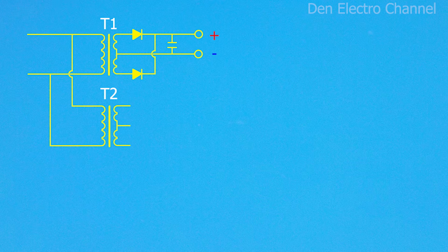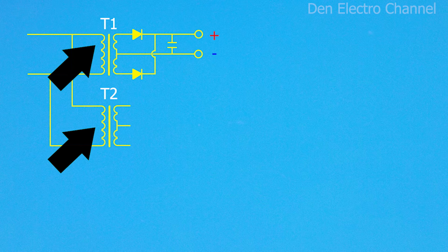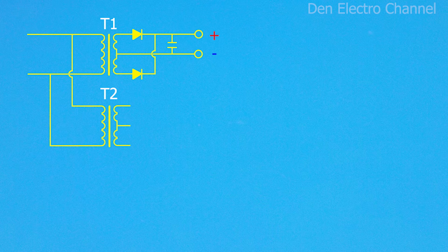The second transformer will be connected to the power supply very simply. We'll connect its primary winding in parallel with the primary winding of the transformer in the power supply. When the power supply turns on, current will flow to both transformers at once.